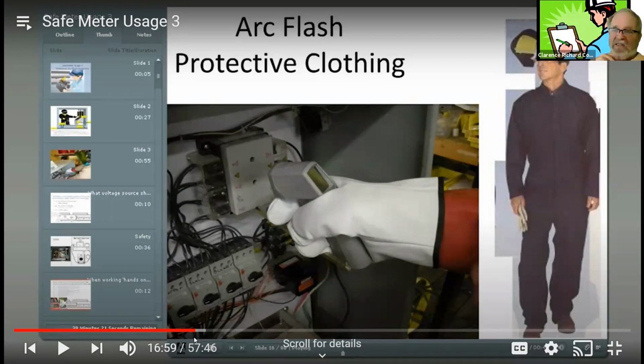Because the heavy stuff gets so bulky, I try to do my troubleshooting in what's called an 8 calorie suit. If I do get exposed to any arc flash, it's going to give some protection. It will be enough protection in most of the things that I get into. And if the blast is a little bit bigger than that, it's going to at least protect me from that blast considerably. A lot of things you want to do, protecting your eyes is very, very important.